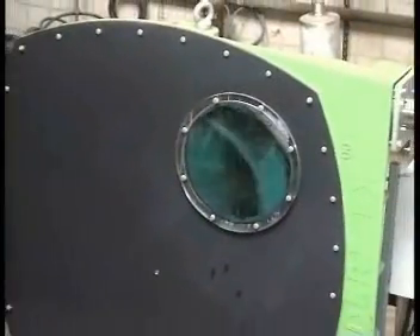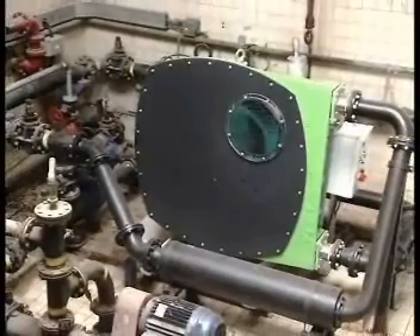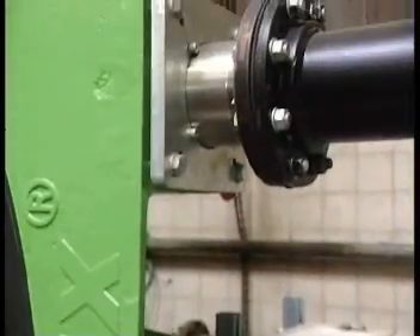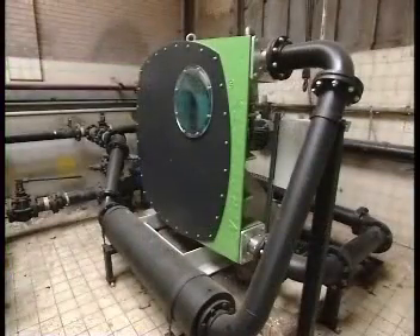Verderflex's largest peristaltic pump is the BF125, with a hose bore of 125 mm. When pumping water, this unit will deliver up to 80 cubic meters per hour, or 350 US gallons per minute, when running at a speed of 40 rpm.